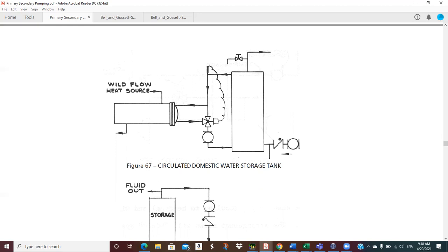While that indicates I have no control, it has plenty of capacity. And then this valve is simply modulating to heat this water up to say 180. If that's my set point, 180, something like that. You might set this at 182 or something just to make sure that you keep up a little bit. But probably if this is a 180 tank, you set this at 180.